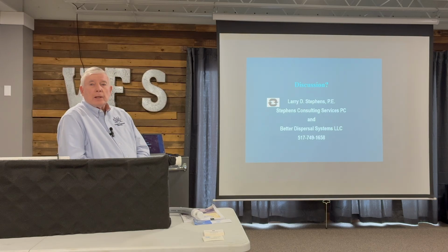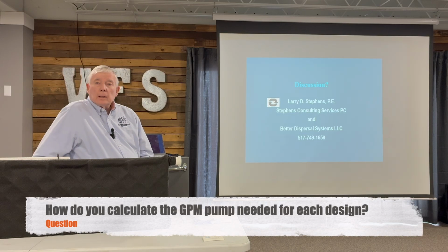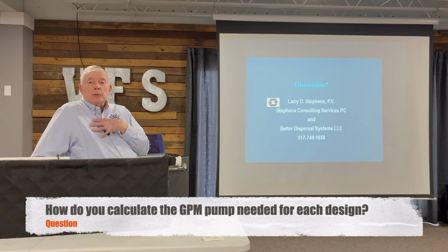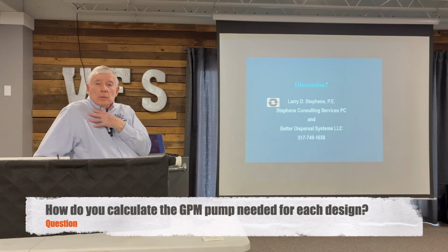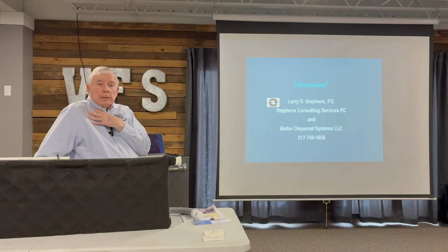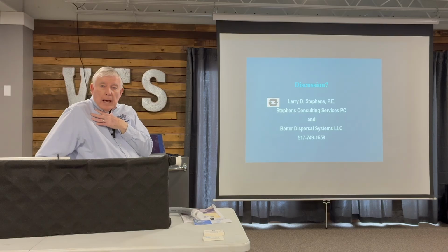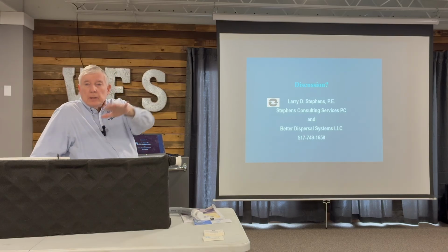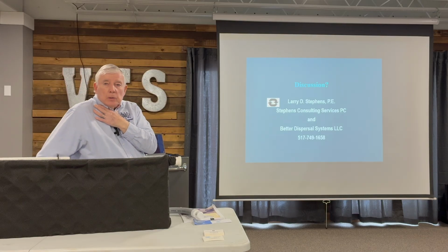Other questions? Yeah, Maynard. Well, the way I do it, I use the Excel spreadsheet that I designed myself. I plug in the lateral information, the number of holes per lateral, and it works not just on this but on other pressure distributions.